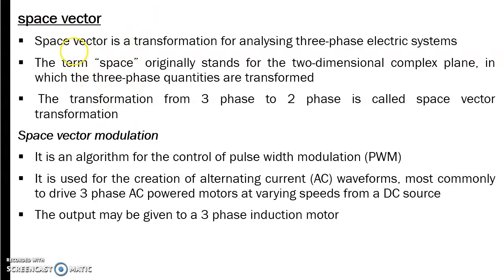And we discussed so many VSI fed induction motor drives in different cases. So in that, if you are using a PWM method for controlling the inverter, we can use this space vector modulation. That is, instead of controlling three phases in the three-phase system, you can use a two-phase plane. So the control becomes more accurate.